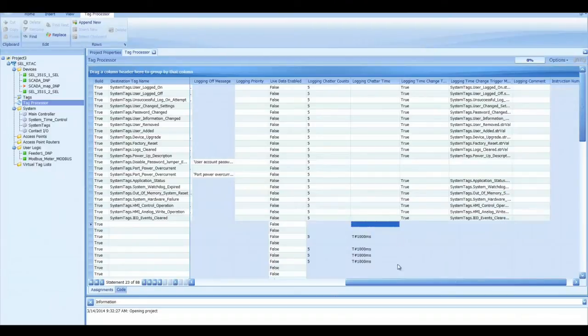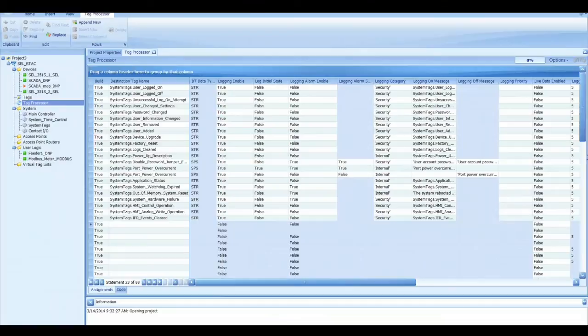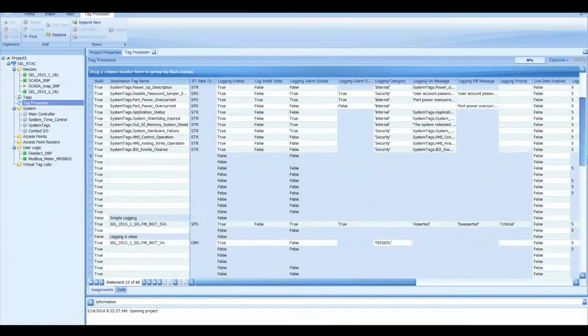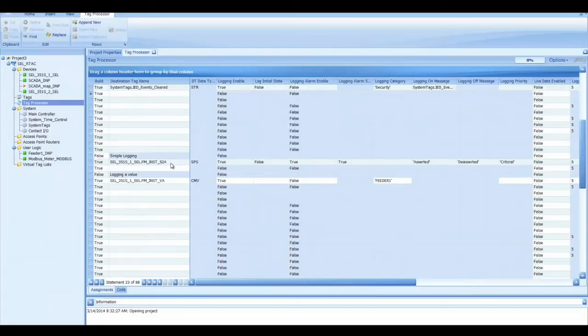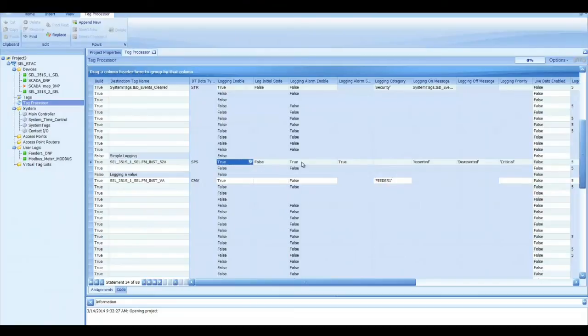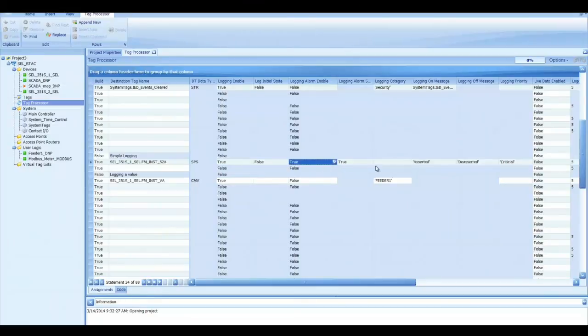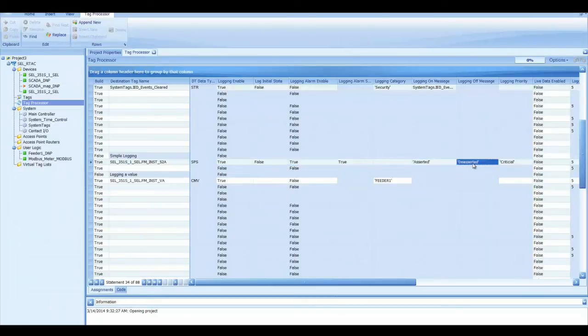So let's scroll down here a little bit more and show an example of logging a specific tag. I've got the 52A bit right here and we want to log whenever that goes true. So I have logging enable set to true. We're going to set logging alarm to true and we're going to log that in the alarm. We're going to have the logging on messages asserted and then logging off messages de-asserted, so that we know when it happened and when it cleared.